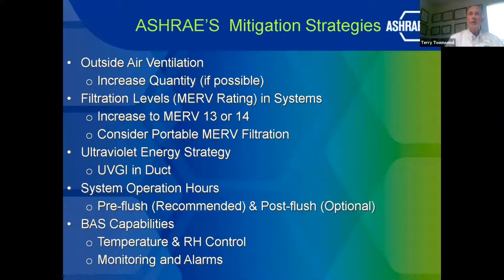So the mitigation strategies: outside air ventilation, increase the ventilation amount if possible, and increase your filtration system from a MERV 5 to 8 to a MERV 13 or 14. And then consider portable MERV filtration. UVGIs in ducts. Pre-flush is recommended. Post-flush, that's optional. And really, at this point, post-flush we're seeing for occupied areas is not really being utilized anymore.